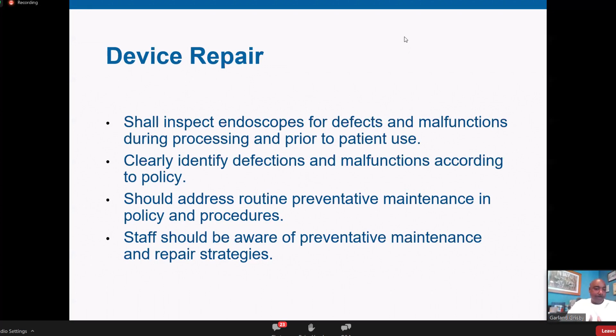Loan scopes. Now, this also should be part of our policy. Even if we get a loan scope from a manufacturer, from the OEM, it's important for us to still inspect that incoming scope. I've had a situation where I received a loan scope that came broken. The angulation was damaged and it failed leak. So it's important to make sure that you inspect it just as you would a scope that's in your facility, even though it's loaned from the manufacturer or a third party. You want to contact the loan company to report that issue.